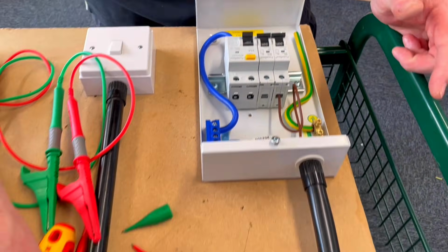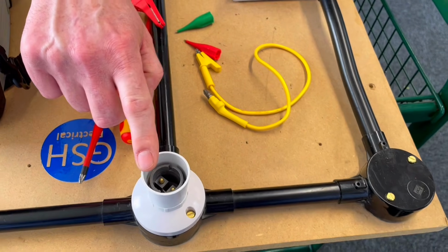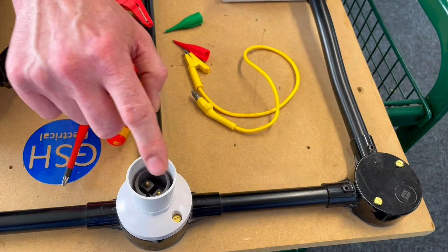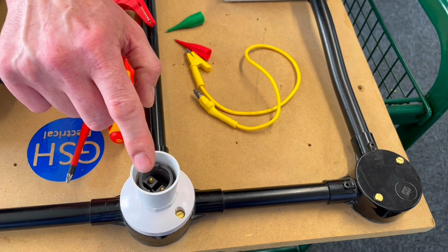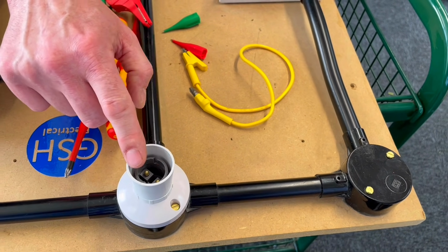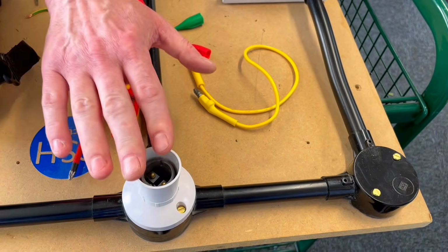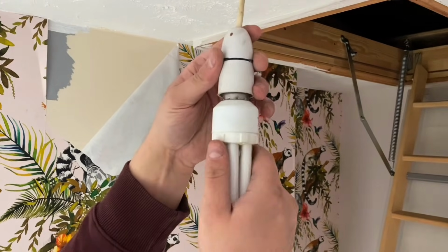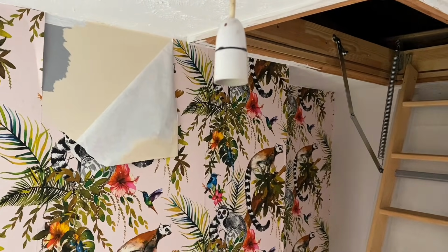The lighting point is back and covers are on, but the lamp itself has been removed. If we had the lamp in here, it would be connected across the 2 pins, and that would be switching line and neutral and would cause you an issue with your reading. So all loads need to be removed because loads are naturally connected across line and neutral. All switches are on, all covers are on.